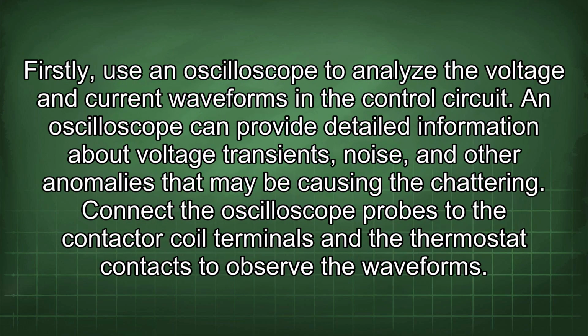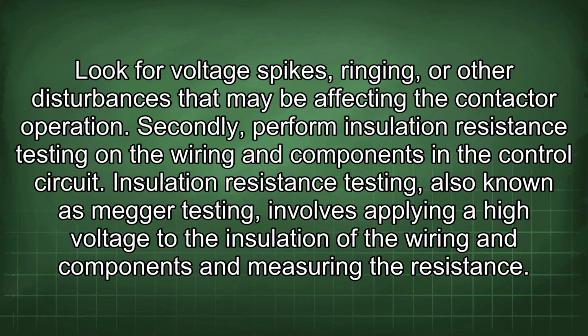Firstly, use an oscilloscope to analyze the voltage and current waveforms in the control circuit. An oscilloscope can provide detailed information about voltage transients, noise, and other anomalies that may be causing the chattering. Connect the oscilloscope probes to the contactor coil terminals and the thermostat contacts to observe the waveforms. Look for voltage spikes, ringing, or other disturbances that may be affecting the contactor operation.